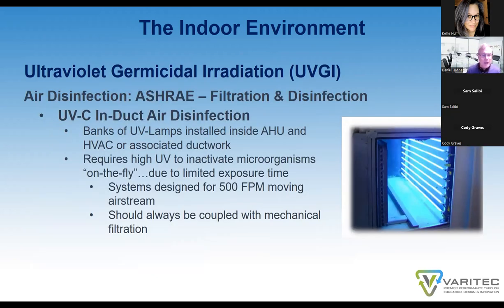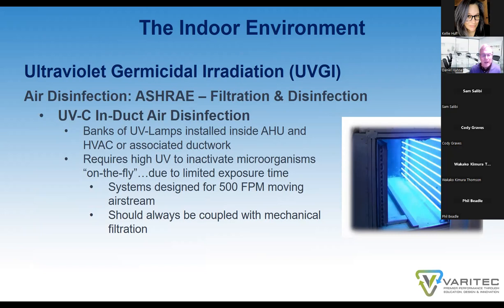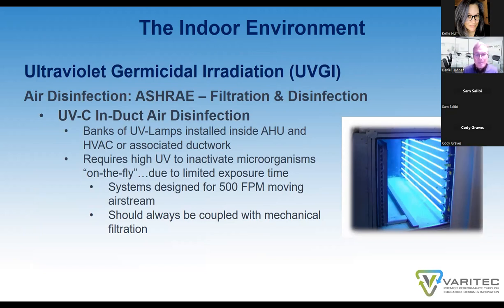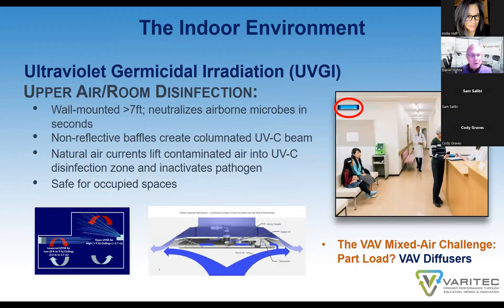These UV lights can also be used on an on-the-fly application, that is to say, mounted in ductwork. We have to be cautious of the actual velocity of the air across the coils. The UV light coils would have to be designed appropriately to be effective in this application, but they can be effectively introduced into return air systems or supply air systems to make sure you have adequate pathogen mitigation in a space. They can also be located in upper levels of rooms in built environments, maybe conference rooms, emergency rooms, etc. They are located above the exposure of any occupants in the space.